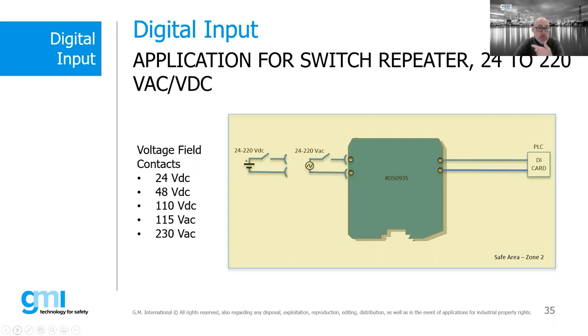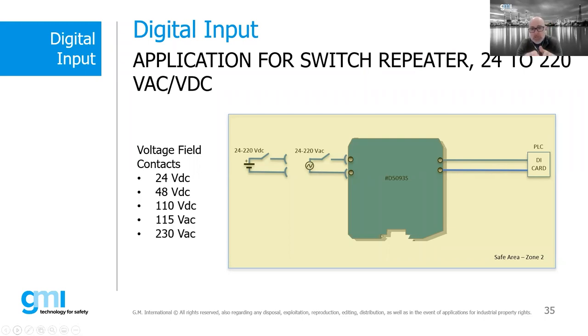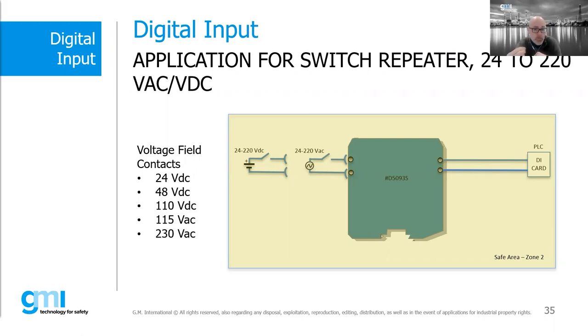A classic example is where you need to communicate a PLC system status between two systems: one PLC's digital output card controls the digital output relay while a digital input card of the other system receives the contact status. The main problem with using a relay for this purpose is that a relay is designed to switch important current values, while toward a digital input system the currents are very low — typically less than 100 mA. This can cause oxidation of relay contacts. It is therefore essential to choose a safety relay with gold-plated contacts, which ensures switching even at currents lower than 10 mA.